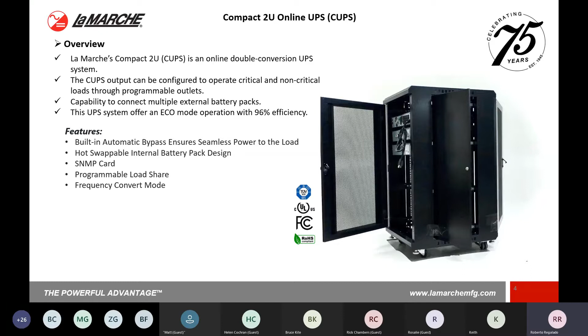Frequency convert mode simply means that if you do run on a DC backup mode, you have the capability of running your output AC in either 60 hertz or 50 hertz. Inversely, if you are running on AC mode and you are running straight bypass, your AC output would follow your AC input that you have. So if it's 60 hertz, it'll follow 60 hertz, 50 to 50.